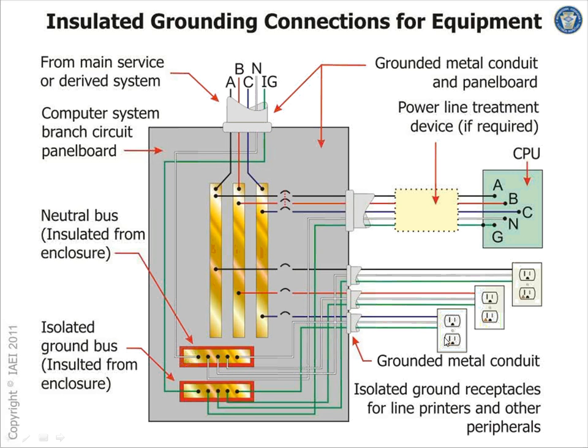It's right here, an orange triangle at every receptacle, grouping them together inside the panel separately. The IT guys don't want them on their racks anymore. They'd rather have a standard grounding system than isolated ground receptacles. Sounds confusing. In the hospital, it's really redundancy in the ground. You're absolutely right, redundancy in the ground.